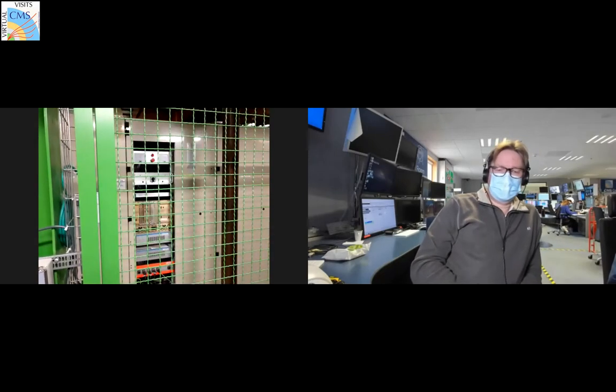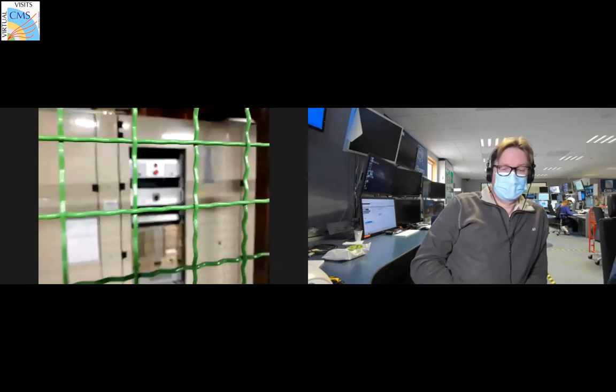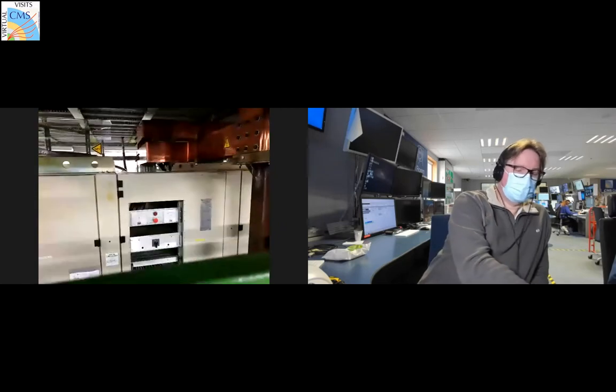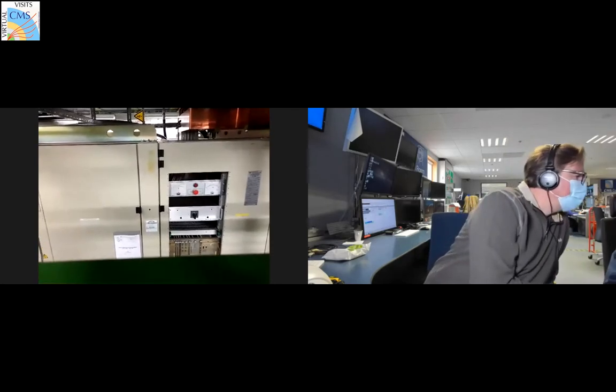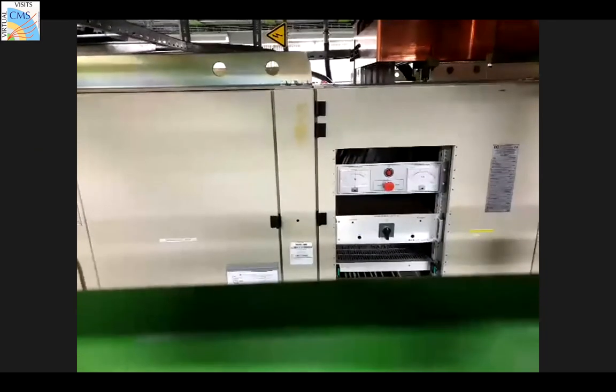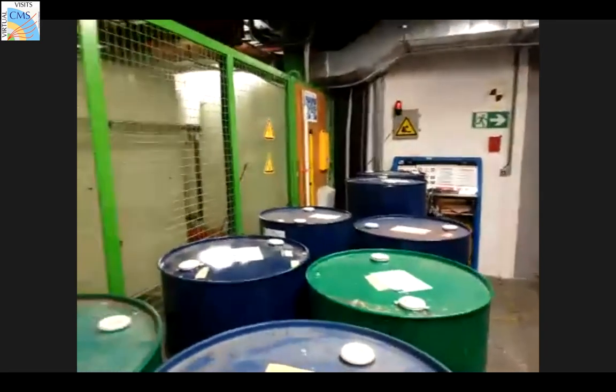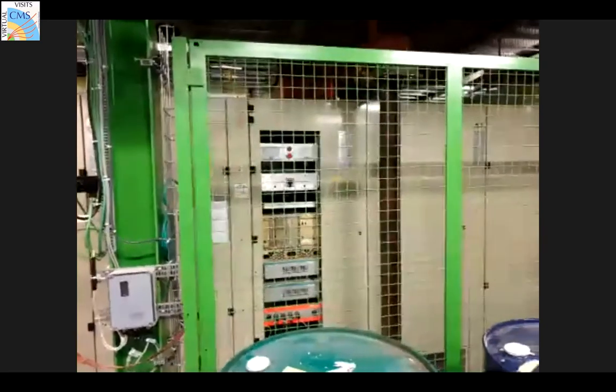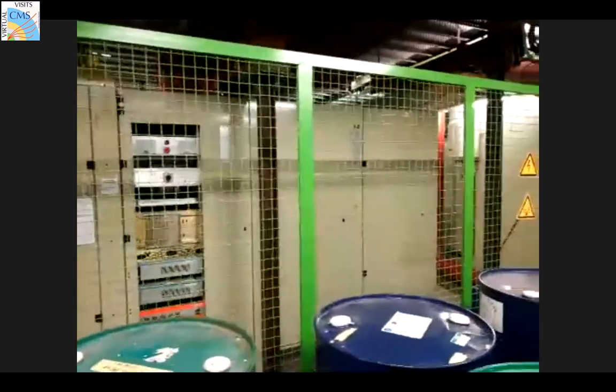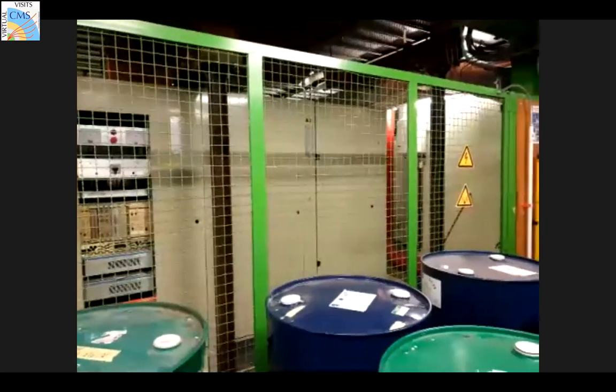And just to say, Klaus, we are right in front of the supply of the power of this magnet. So you see a very nondescript electrical cabinet in the background. You have a voltmeter and an ammeter there, and the ammeter is in kiloamps, and its scale goes all the way up to 25, because a nominal field of 3.8 Tesla, as Klaus mentioned, we're going all the way to 18,000 amps, which is still indicated in this rather nondescript cabinet by the needle going to 18,000 ampere. So that's where the main power is supplied. But then please go into the details.